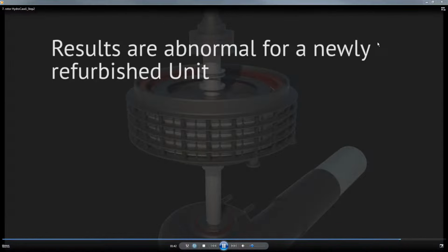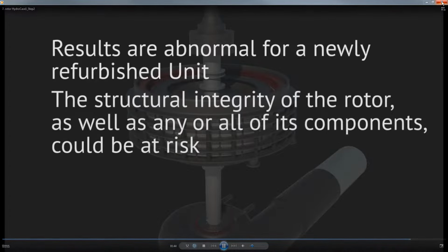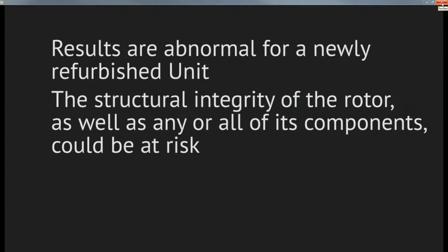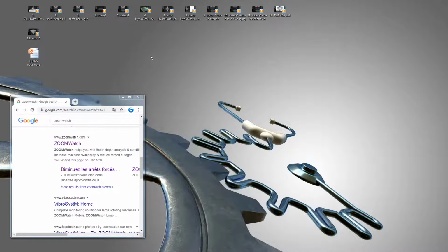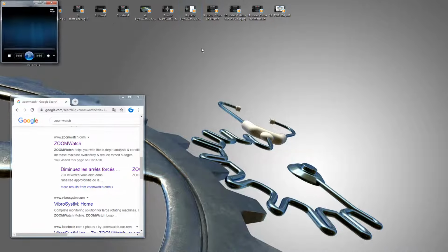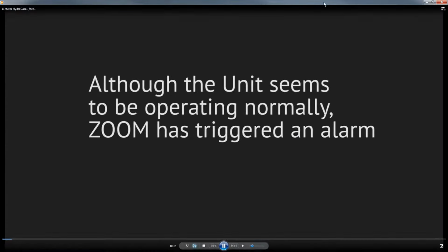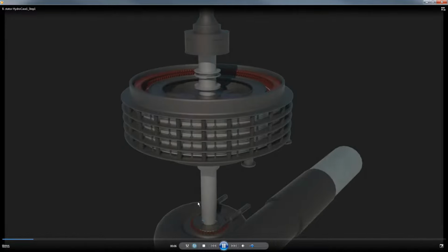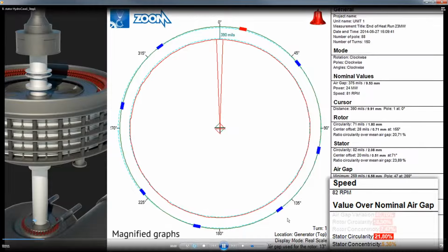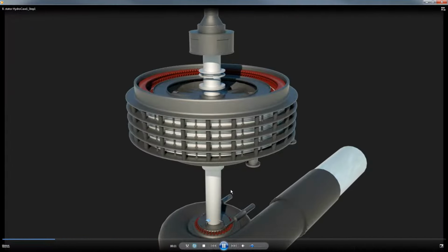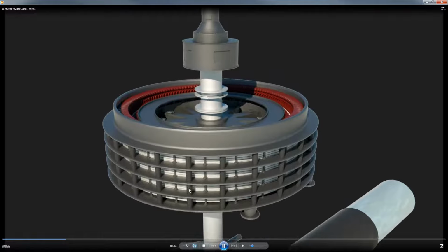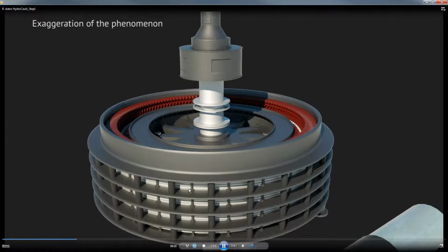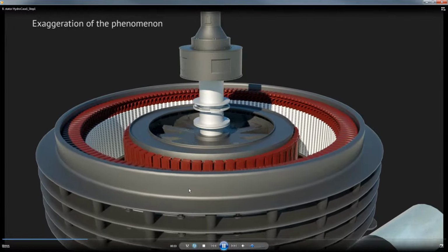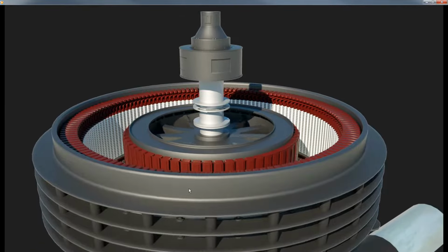Okay, so that was from the perspective of the rotor. Obviously, there was some discussion between the utility and the manufacturer. And I want to show you what happened to the stator during those same measurements. Okay, so again, the unit seemed to be normal. And Zoom triggered some alarms, and we could see the stator circularity was very high. So again, we're going to exaggerate the phenomena just to emphasize the shape so you can see the distortion.